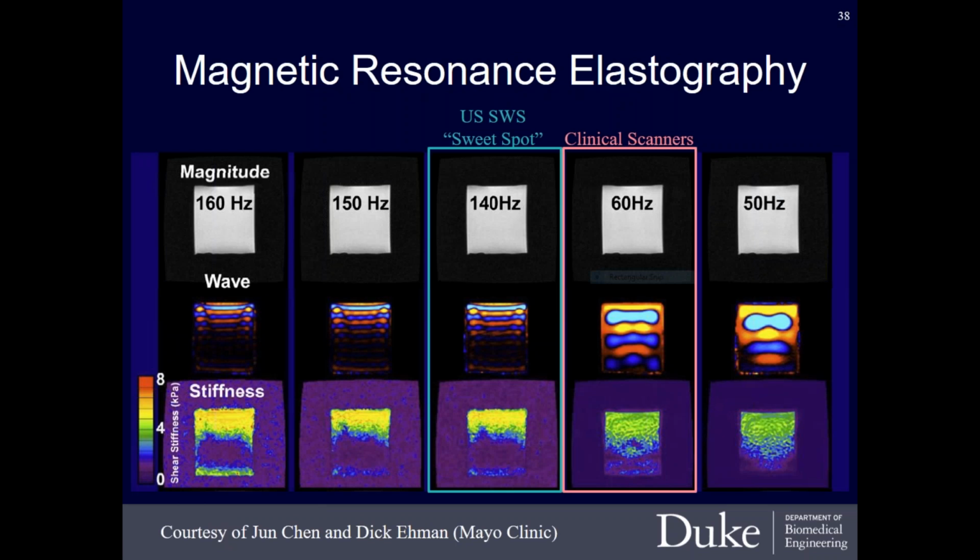I wanted to quickly touch on another non-ultrasonic modality that has traction in the literature for the same purpose, and that also we're trying to, through QIBA, compare to, which is magnetic resonance elastography. Unlike the ultrasonic modalities, instead of using something like acoustic radiation force, MRE actually uses an external vibration source to create shear waves within a material, and then they can reconstruct the resultant equivalent shear wave speed by looking at those wavefronts propagate.